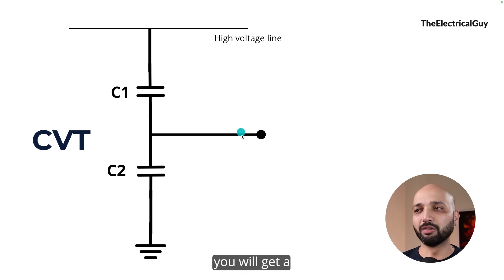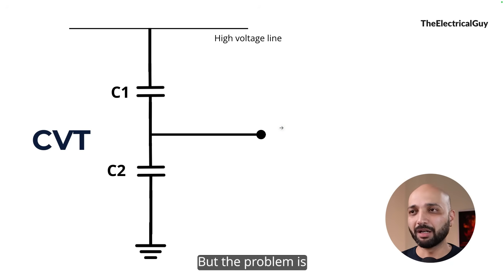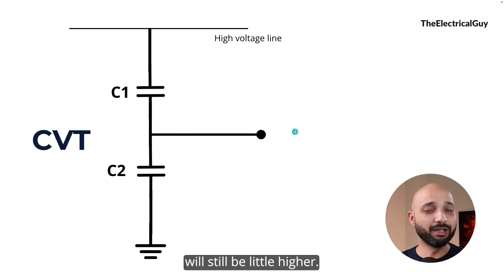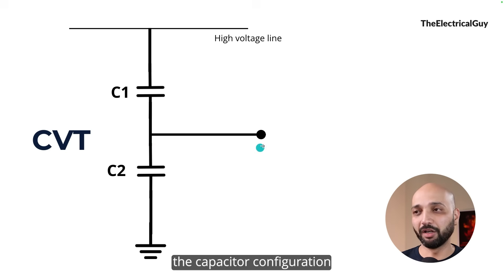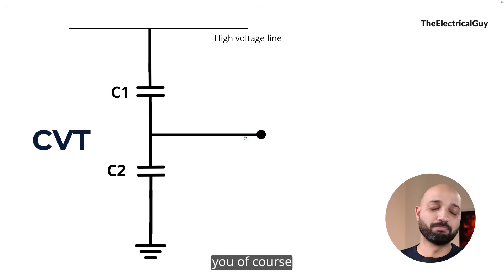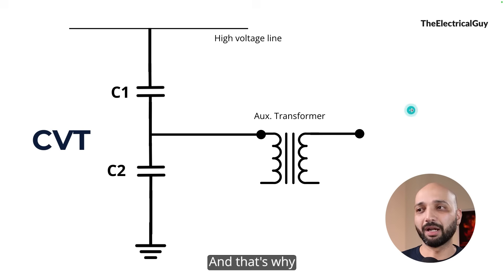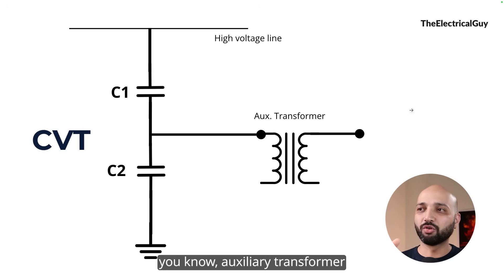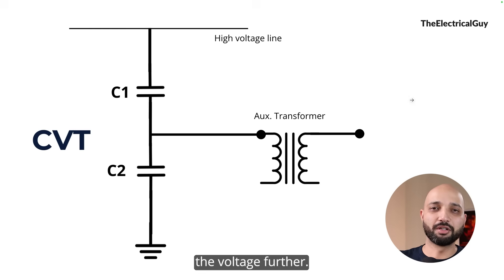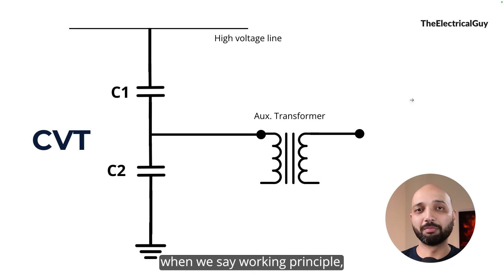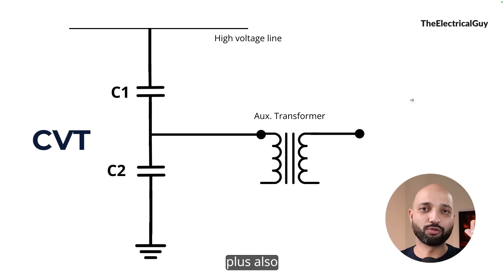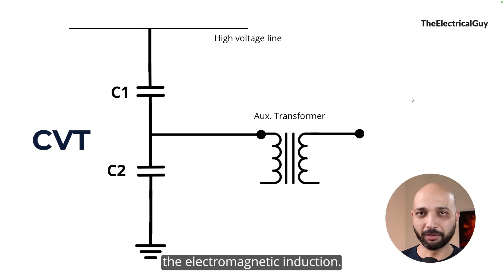When you connect a tap in between the capacitors, you get a much lower voltage. However, this intermediate voltage will still be somewhat high — maybe 10 kV, 15 kV, or 20 kV depending on the capacitor configuration. You cannot give that voltage directly to relays or meters, so we further step it down using a small auxiliary transformer placed at the bottom of the CVT. That's why the working principle of CVT involves both voltage division by capacitor and electromagnetic induction.